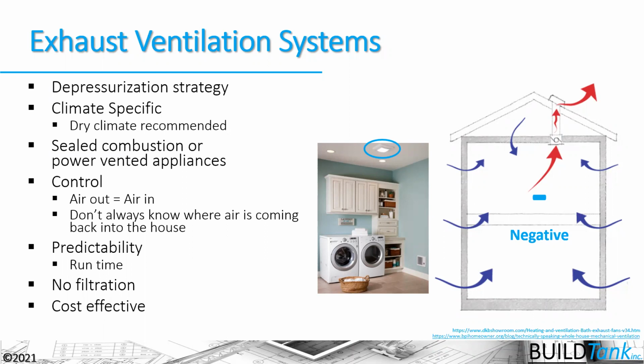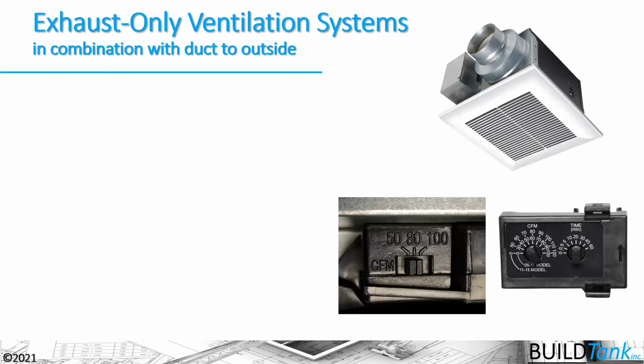So in dry climates like Colorado and Phoenix and areas in the Southwest, exhaust ventilation is used a lot. It's often used with an upgraded fan that's located in a laundry or a centralized bathroom. The big place you don't want to put it is in the master suite, because they do run continuously, or if they're running intermittently, they run a lot. They're very quiet fans, but they do have some noise. So we want to make sure that folks aren't turning them off. There are devices inside of these higher quality fans that you're going to replace that standard bath fan with, so you can adjust the CFM flow and the runtime of the fan so that you can meet the ASHRAE or code required flow rate for that ventilation system.